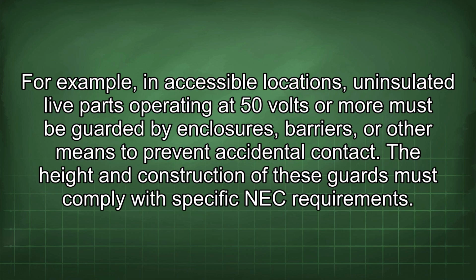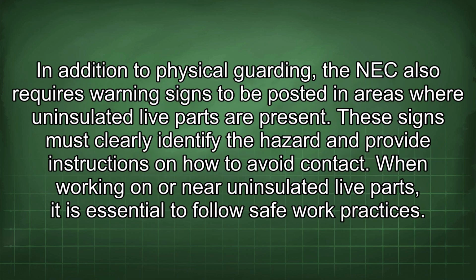For example, in accessible locations, uninsulated live parts operating at 50 volts or more must be guarded by enclosures, barriers, or other means to prevent accidental contact. The height and construction of these guards must comply with specific NEC requirements. In addition to physical guarding, the NEC also requires warning signs to be posted in areas where uninsulated live parts are present. These signs must clearly identify the hazard and provide instructions on how to avoid contact.